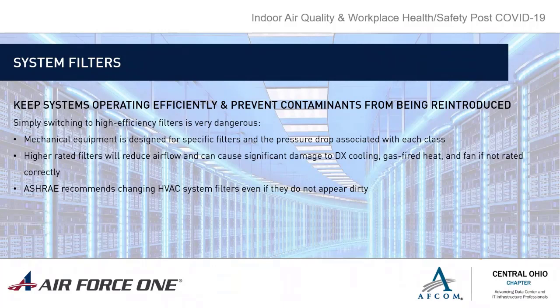And Brian, would you like to expound on that slide? Bottom line, as you go up in filter rating, your pressure drop goes up and the amount of airflow to the system goes down. Now, some equipment, depending on fan design, you can up the speed in your VFD, change your pulley rating, and get the same amount of airflow at the cost of a little extra work. When you're talking about chilled water and hot water systems, it's not such a big deal if your fan's moving a little less air, because you're just not going to have quite as much effectiveness in your space when it comes to heating and cooling.